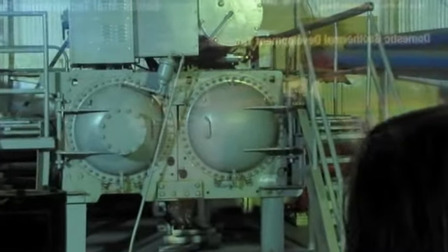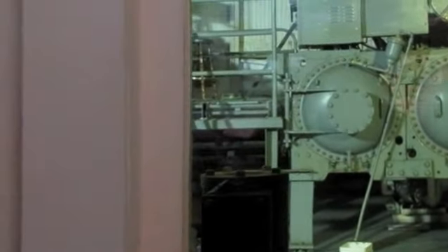The reason we can do that is because we're not using our water to steam. We're using our water to steam something else. So we're basically just running through our system for a short time before we're pumping it right back down. Now we pump that water about 3,500 feet laterally from where we pull it out. So by the time it mixes and gets back to where we're pulling it out, it's right back up to 165 degrees. So in essence, we're just reusing the same water over and over as well. We're not putting any greenhouse gases into the air, nor are we harming our aquifer. That's the way geothermal should be done, and if we have our way, that's the way the other plants around the world will eventually switch over to that.